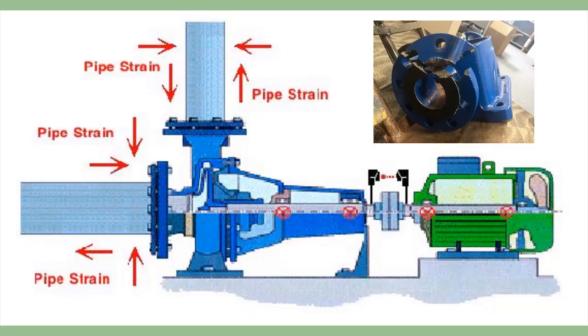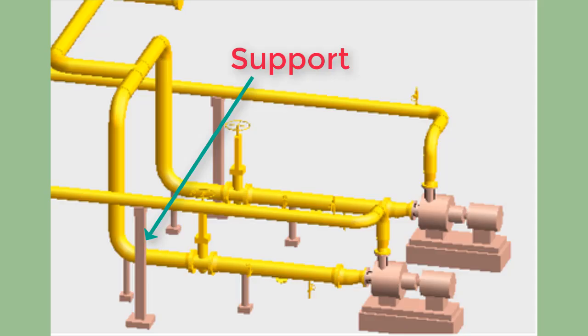Last, number six, ensure the piping arrangement does not cause strain on the pump casing. Pumps should never support the suction or discharge piping. Any stress on the pump casing by the piping system greatly reduces pump life and performance.